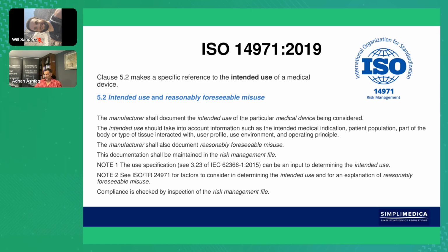Some of the type of things that it asks is, what is the intended use and how is the medical device to be used? And then below that, it goes on and mentions a number of factors that you should consider. And then it basically takes the definitions of the medical device that we've looked at. What is the medical device's role relative to? Is it diagnosing, preventing, monitoring, treatment, all that stuff, right? And then it goes on.